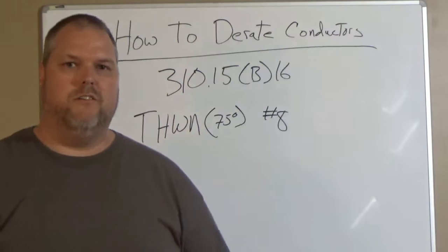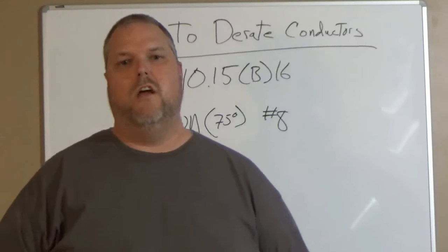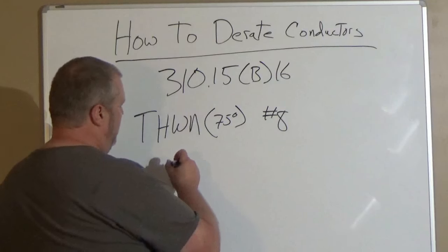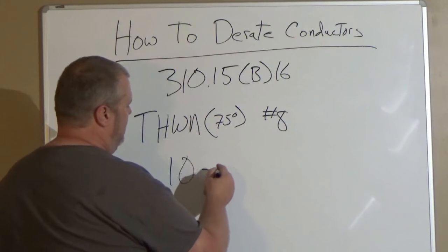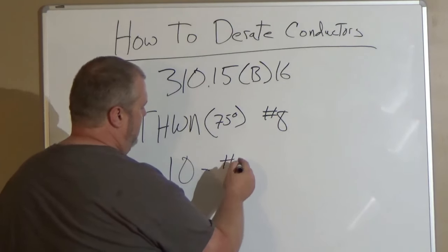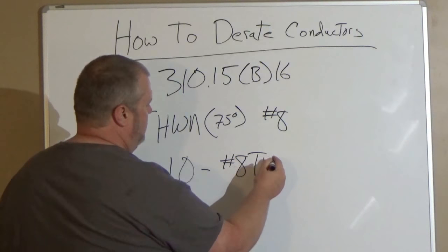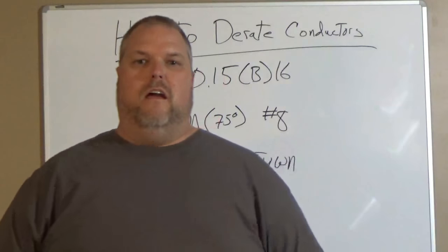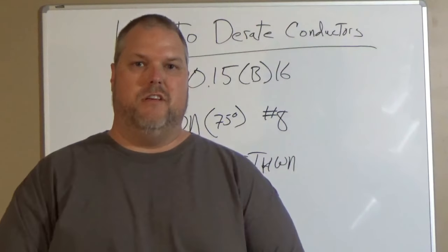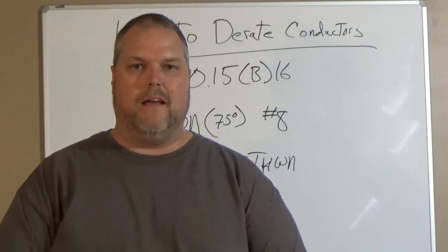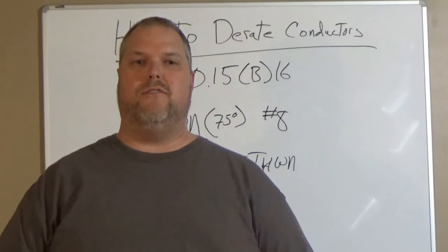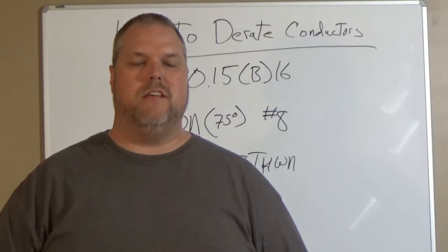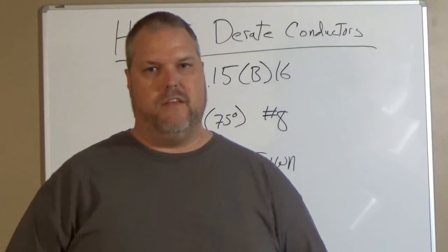Let's stay with the same conductors. What we're going to do is now we're going to put it in a conduit because now there's 10 number 8 THWN. If I have now 10 conductors in that, when I go back and I look at 310.15.B.3.A, that's going to tell me that now I have to take it at 50 percent.